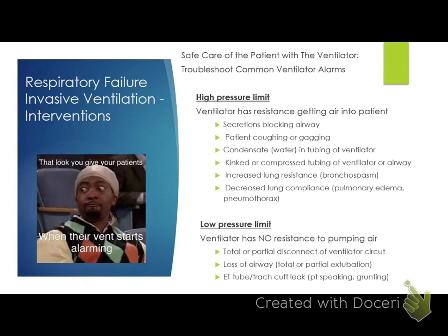And here are the alarms that you will need to know. High pressure limit: here's the reason, the ventilator has resistance getting the air to the patient. Low pressure limit: no resistance to pumping air.